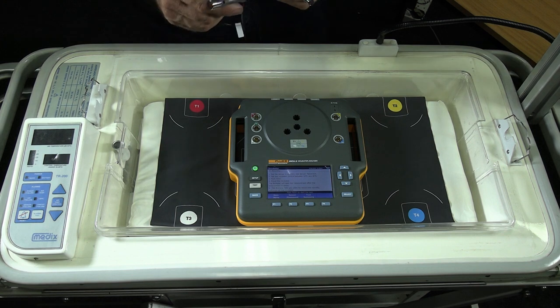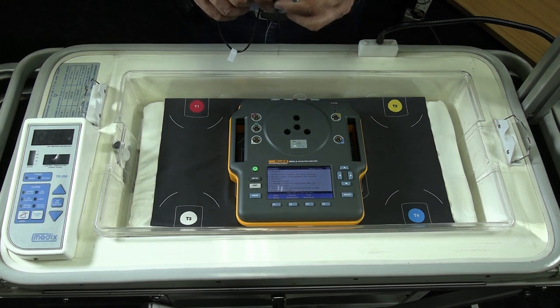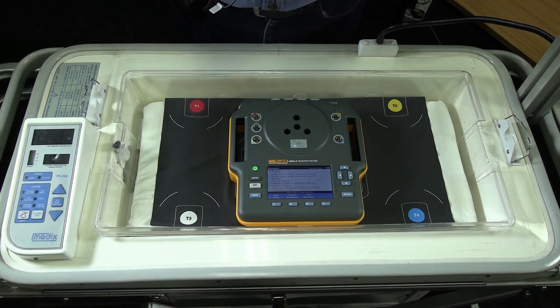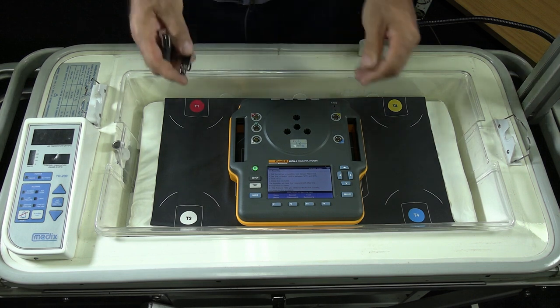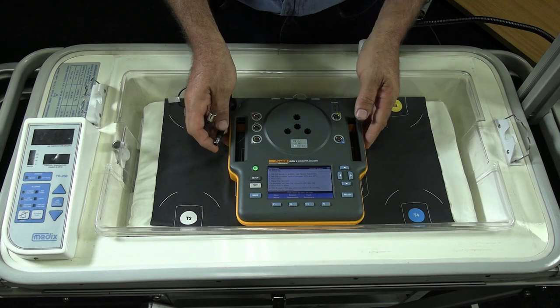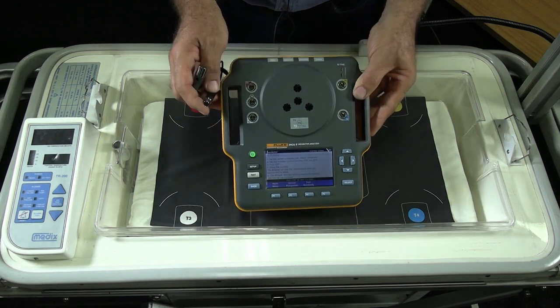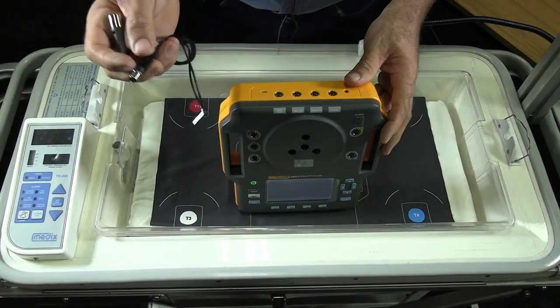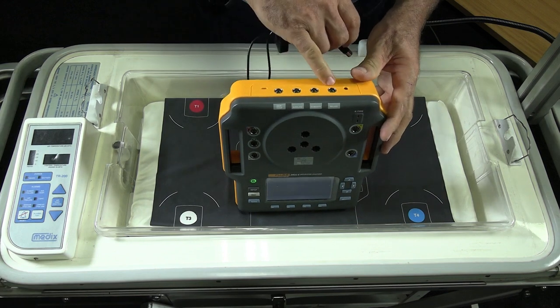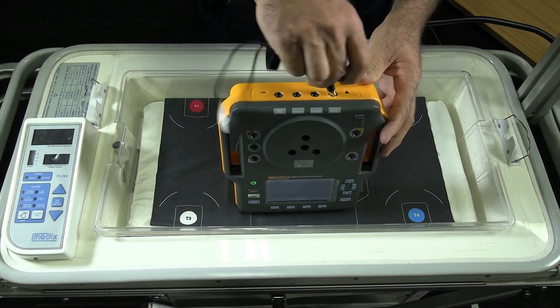The next test we want to do is make sure that the alarm sound, the sound coming from the fans of the unit, and the environmental sound outside the unit is within comfortable specifications for the baby. Because we know that whenever a baby is comfortable, healing takes place much quicker. Again, the sensor plugs in at the back. We look for the sound position.